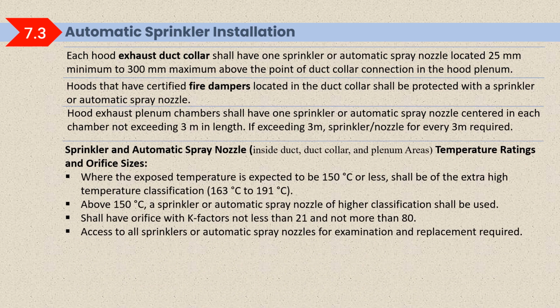Sprinkler and automatic spray nozzle inside duct collar and plenum area, temperature rating and orifice size: where the exposed temperature is expected to be 150 degrees centigrade or less, it shall be of extra high temperature classification, 163 degrees centigrade to 191 degrees centigrade. Above 150 degrees centigrade, a sprinkler or automatic spray nozzle of higher classification shall be used. Shall have orifice with K factor not less than 21 and not more than 80. Access to all sprinkler or automatic spray nozzles for examination and replacement.